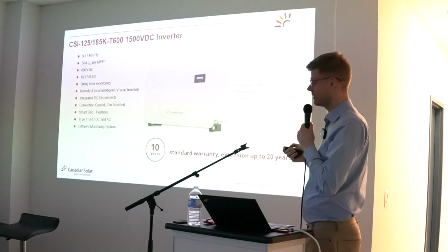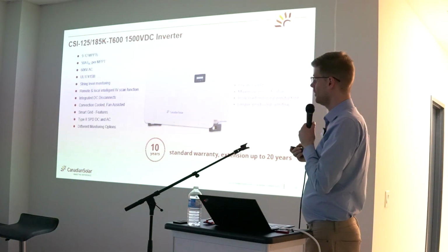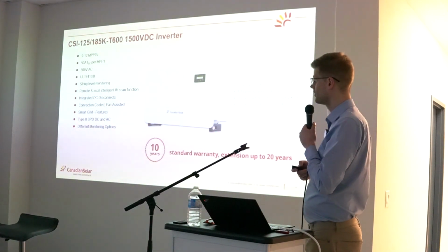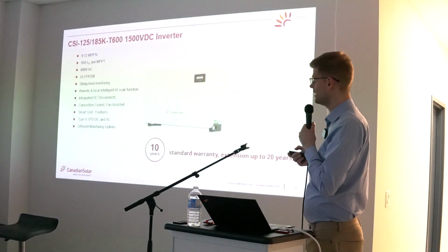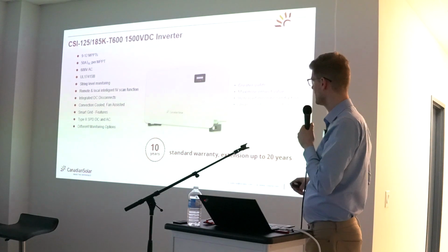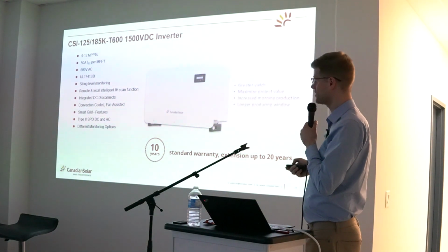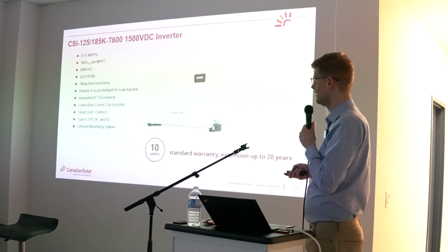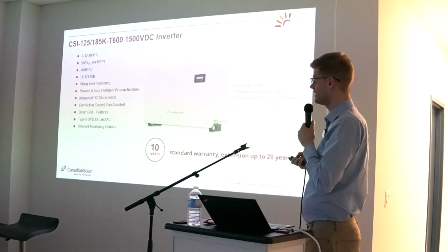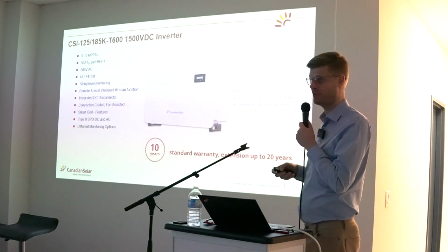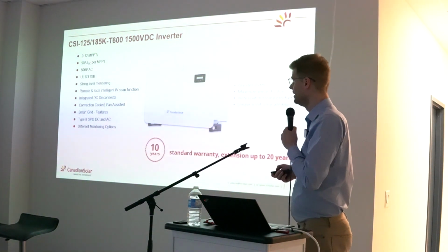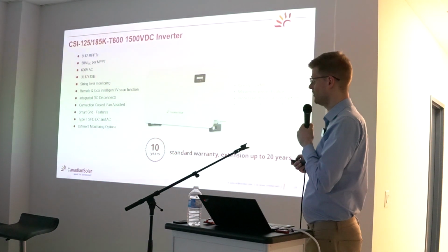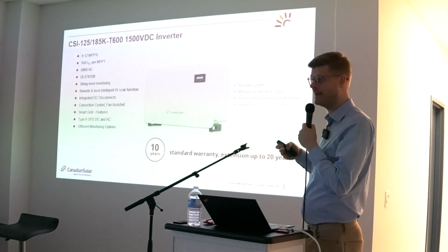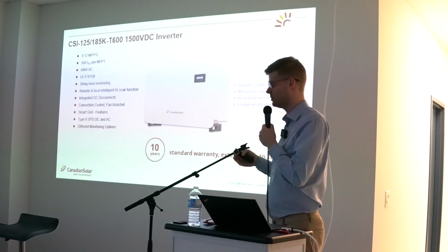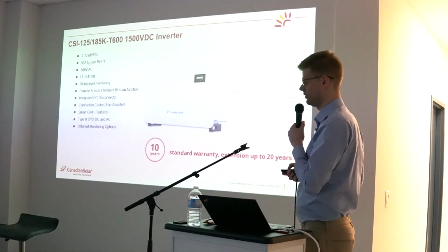You have string level monitoring available for every string. You have the remote IV curve tracing functions, DC integrated disconnects. You have a total of 6 disconnects for the big units or 5 disconnects for the small. It's a convection cooled system that is fan assisted. Smart grid features already fully implemented under that UL 1741 SB umbrella. You have different monitoring options and you have very capable DC and AC overcurrent protection, overvoltage protection, built into the inverter already.